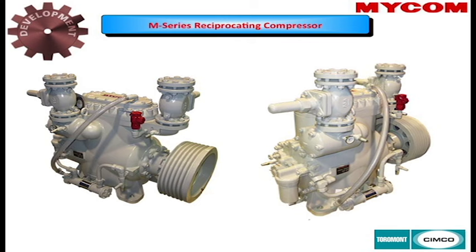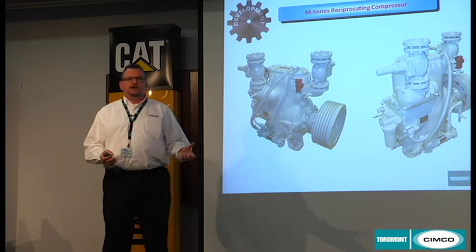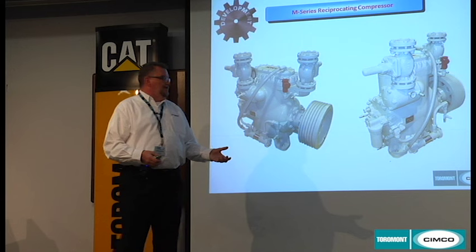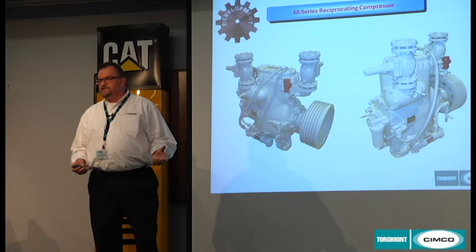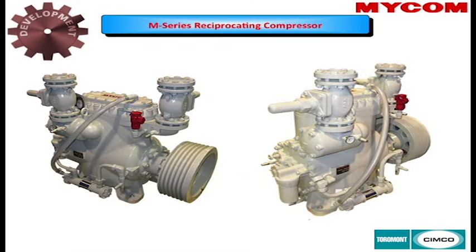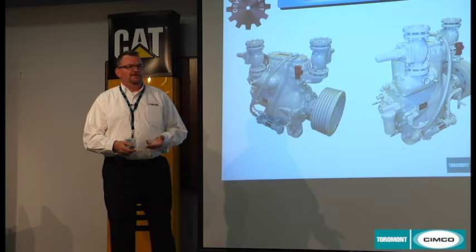What Mycom wanted to do was develop a more energy-efficient compressor for the world marketplace — that is our M compressor. There's a six-cylinder M compressor and a two-cylinder, which is most common in Ontario arenas. In Ontario, typically smaller compressors in multiples are used, partly due to the Operating Engineers Act which limits horsepower. The 2M was more or less developed as a replacement for the 4WA, 6WA, and up to an 8WA at about 1,100 RPM.